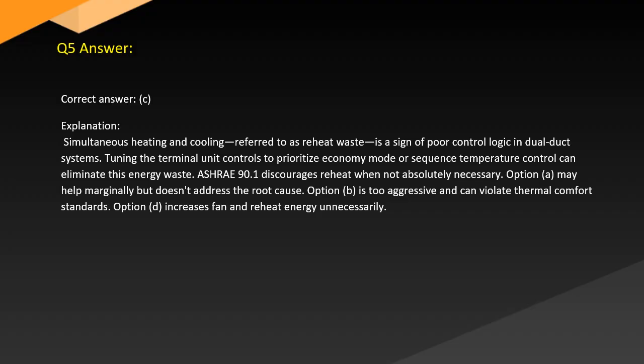Answer. Correct answer: C. Explanation. Simultaneous heating and cooling, referred to as reheat waste, is a sign of poor control logic in dual duct systems. Tuning the terminal unit controls to prioritize economy mode or sequence temperature control can eliminate this energy waste, and ASHRAE 90.1 discourages reheat when not absolutely necessary.